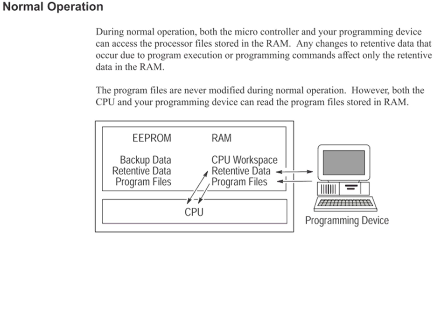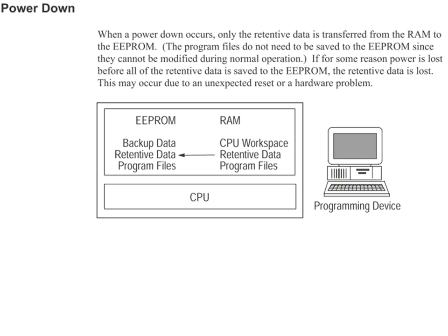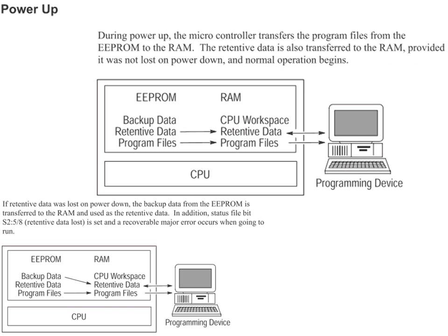While the PLC is operating, you can see what's happening on the PC, and we'll see some examples of that once we start the programming. And then when the processor is powered down, the information in the RAM is put into the programmable memory so that it's retained, so that you don't lose it. And power up is just the opposite. Any data that was written into the EEPROM is put back into, if you want to think of it as the workspace, the RAM.